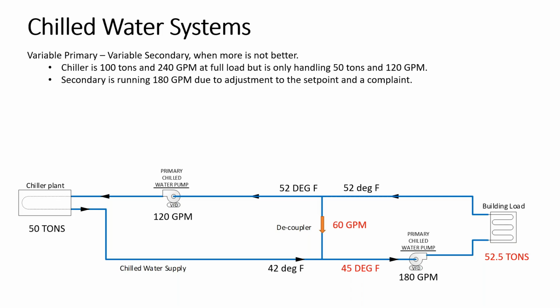However, somebody complained and said that they weren't cooling very well, so somebody upped the flow on the secondary. They increased the flow on the secondary to 180 GPM. So now the secondary is pumping more water than the primary provides. And so what's happening, you've got flow going backwards through the decoupler. You're mixing the 52-degree return water from the building with the 42-degree supply water coming from the chiller, and you're sending 45-degree water out to the coils.